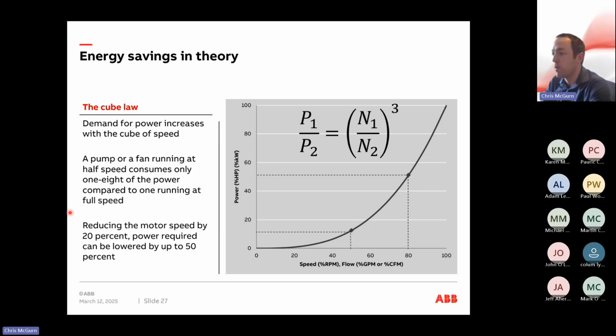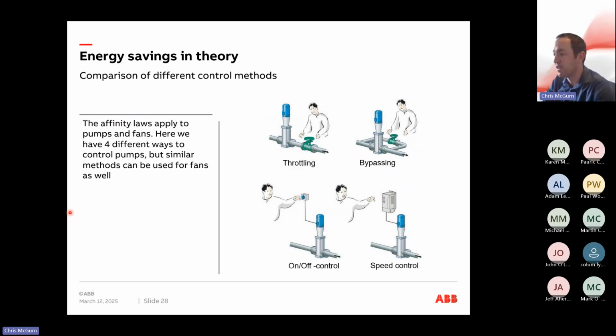So this cube law is applicable to pumps and fans, those types of applications, which is why it's so important that those are considered when you're looking at your energy savings. So like I said earlier, the affinity laws apply to pumps and fans, but there are different control systems that are used. Traditionally, mechanical control systems such as throttling, where you just slow down the flow physically through a butterfly valve, bypassing, where it flows back and forth around the motor itself, and on-off control, so just switching it on and then switching it off as and when it needs.